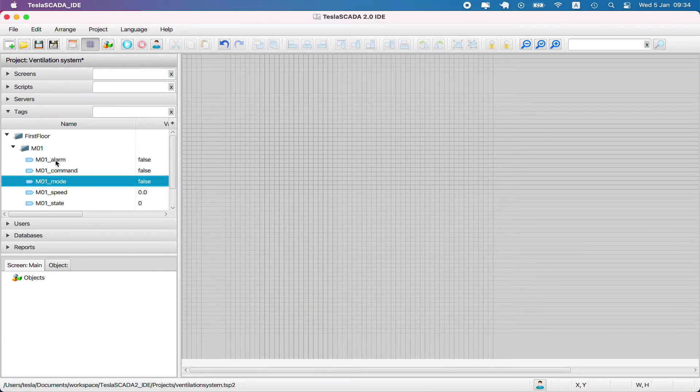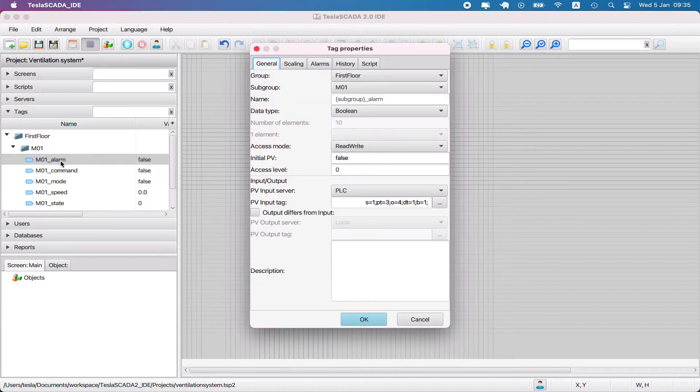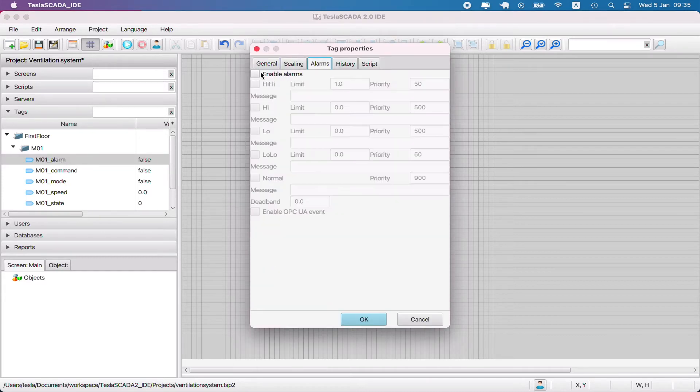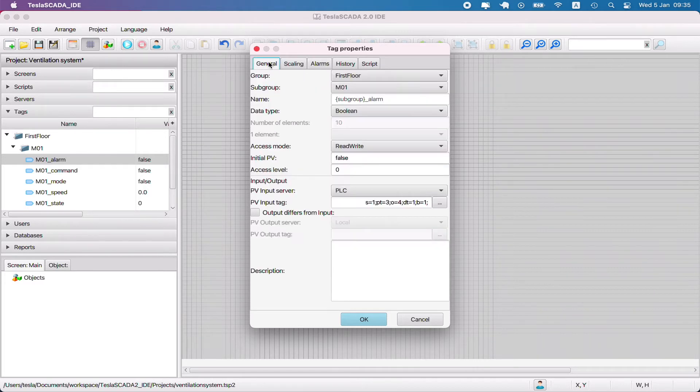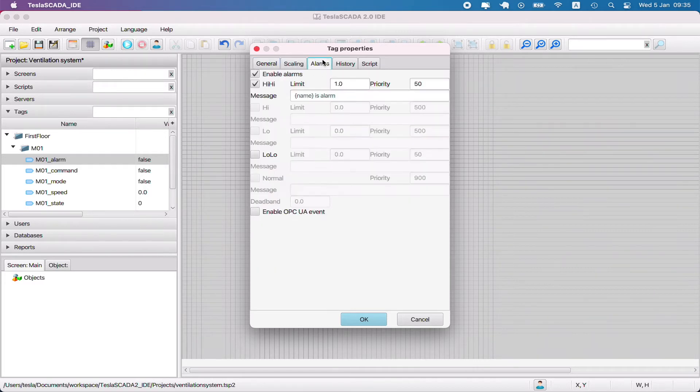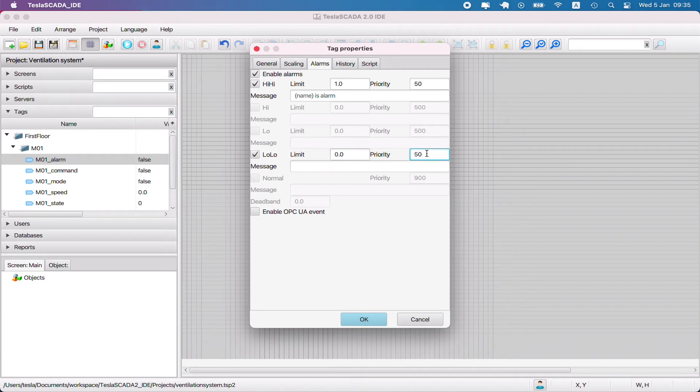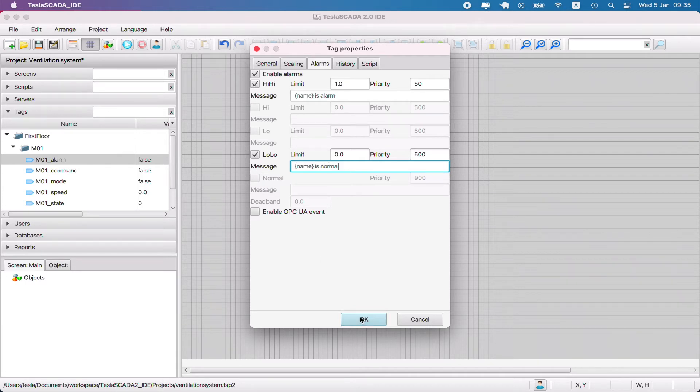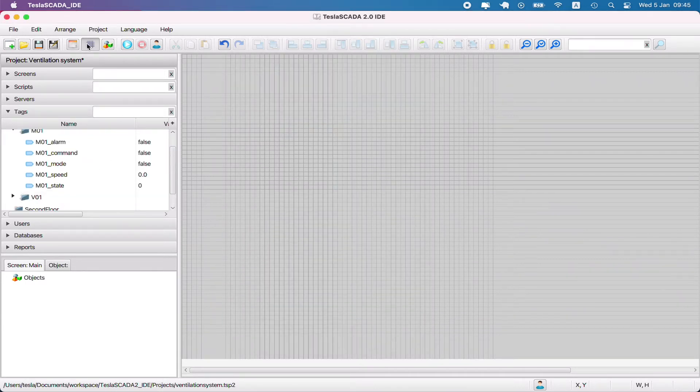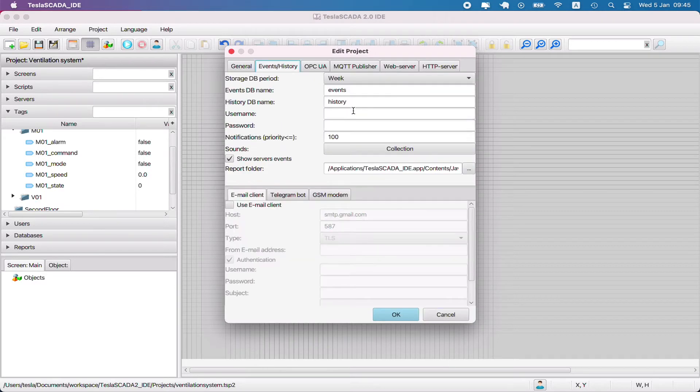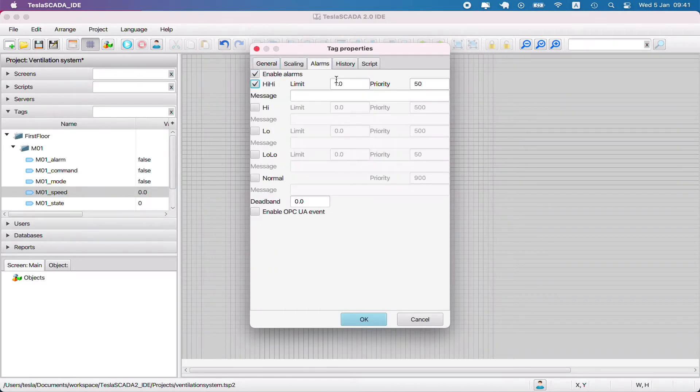Now we have to set up alarms for our alarm tag. Let's get to the alarms tab and enter messages. We enter messages depending on the name of the tag - for this we use the name keyword. Set up low low alarm message and set priority 50 because we don't want the alarm dialog box to appear.